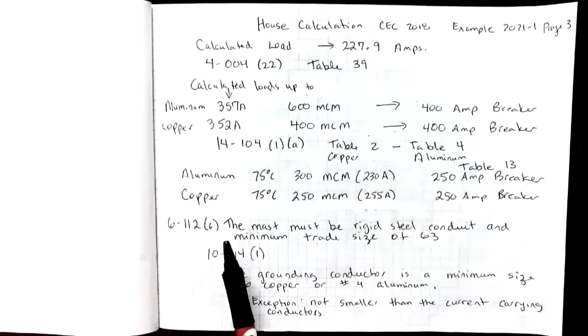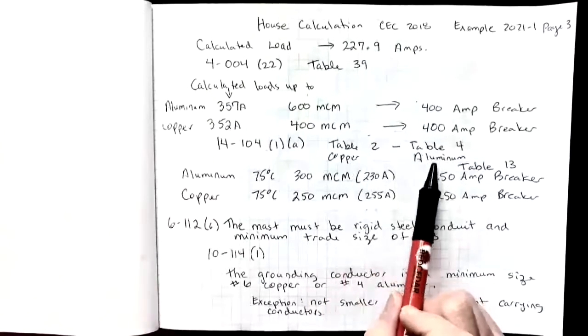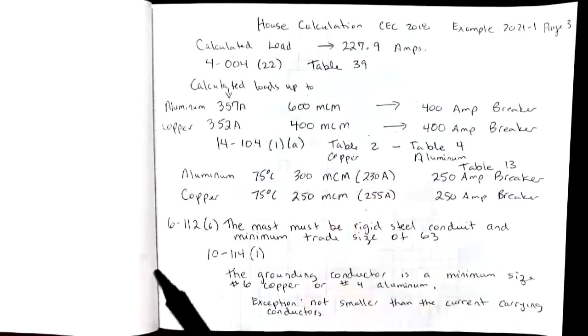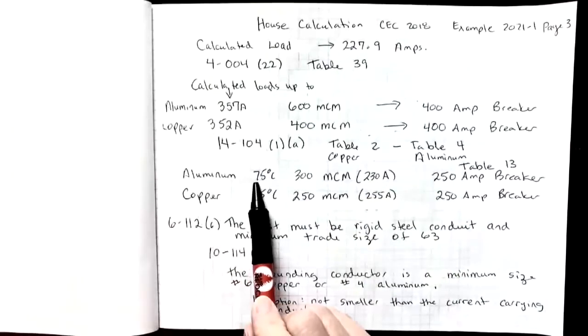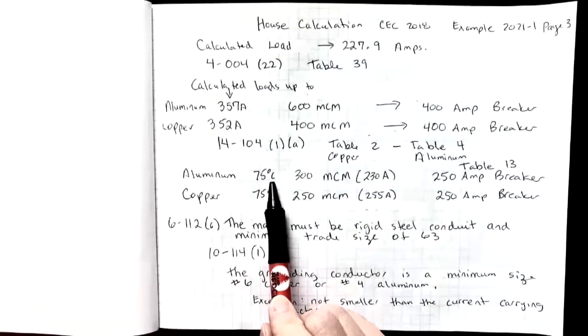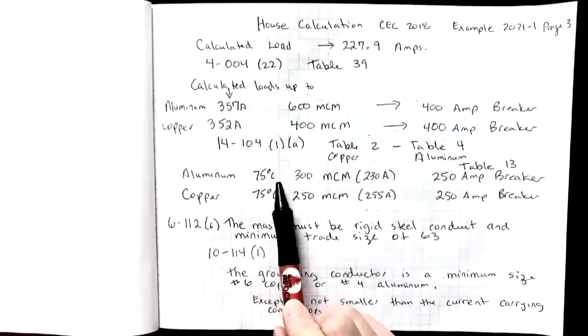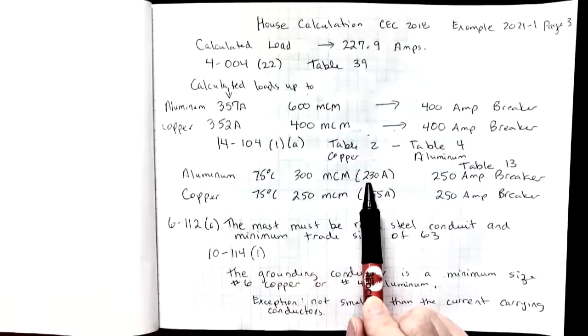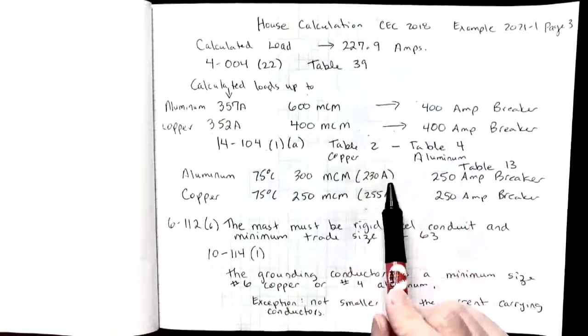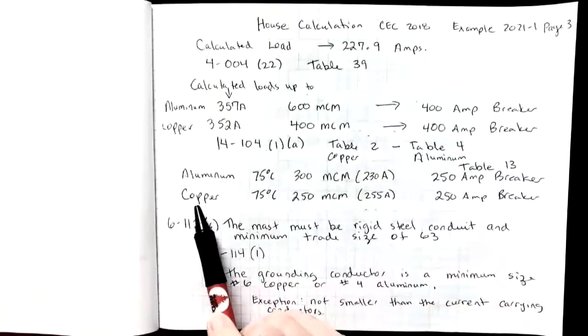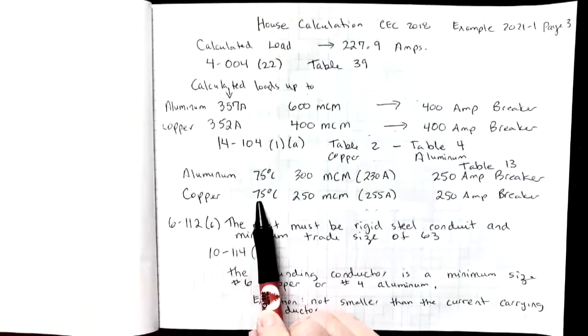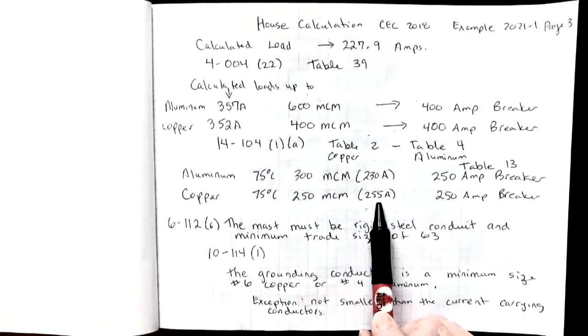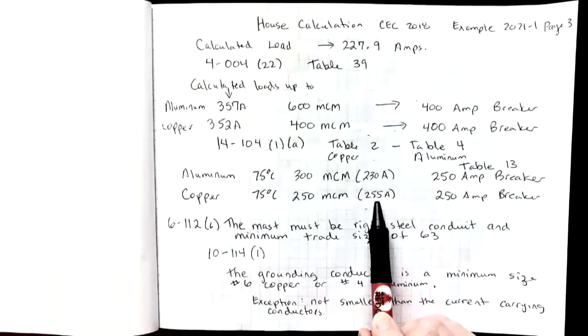I'm going to go and look in table 2 for copper, in table 4 for aluminum, and see if I can find a wire that will just carry that load. When I go to table 4 for aluminum in the 75 degree column because our breaker and our equipment is limited to 75 degrees, I see that I could actually use a 300 MCM wire. That would be good for 230 amps. My load is only 227.9. That would carry my load. Or if I'm looking for copper, I would go to table 2, 75 degree column again, and I could actually see that the 250 MCM copper wire would be good for 255 amps. So either one of those two wires would work.